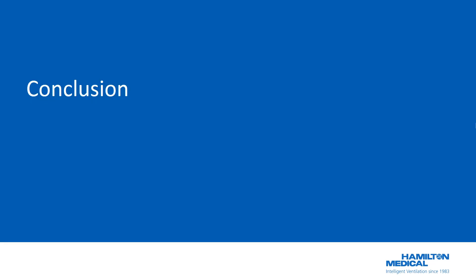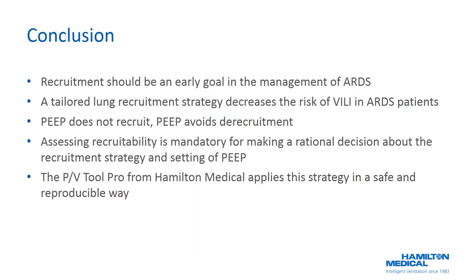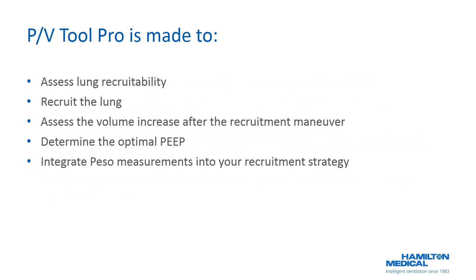Recruitment should be an early goal in the management of ARDS. A tailored lung recruitment strategy decreases the risk of ventilator-induced lung injury in ARDS patients. PEEP does not recruit — PEEP avoids de-recruitment. Assessing recruitability is mandatory for making a rational decision about the recruitment strategy and setting of PEEP. The PVTool Pro from Hamilton Medical applies the strategy in a safe and reproducible way, and is made to assess lung recruitability, recruit the lung, assess the volume increase after the recruitment maneuver, determine the optimal PEEP, and integrate esophageal manometry into your recruitment strategy. This concludes training on the PVTool Pro function for Hamilton Medical Ventilators.